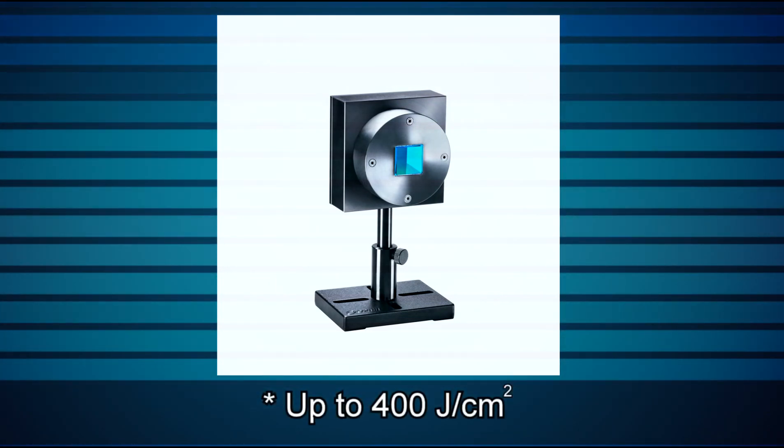3. High energy and energy density, or fluence. The sensor can measure pulse energies up to 2,000 joules, and can handle fluences up to 400 joules per square centimeter for pulse widths typical of IPL sources. This gives you a very comfortable safety margin.